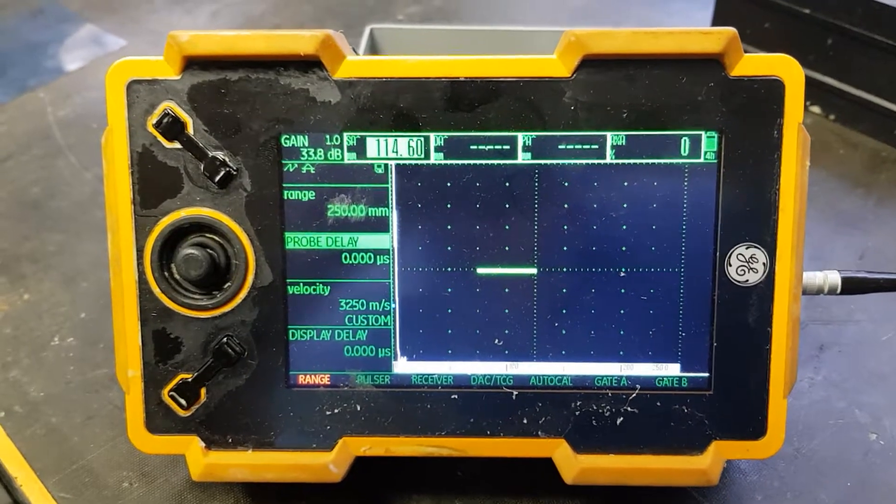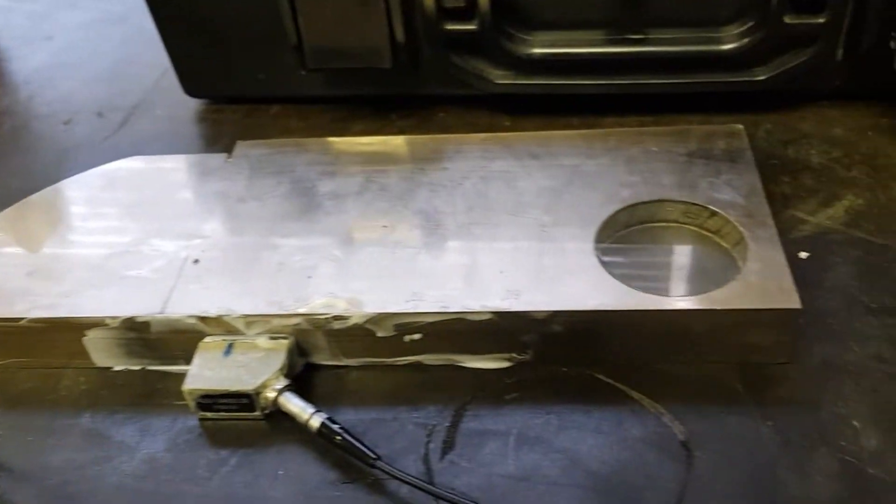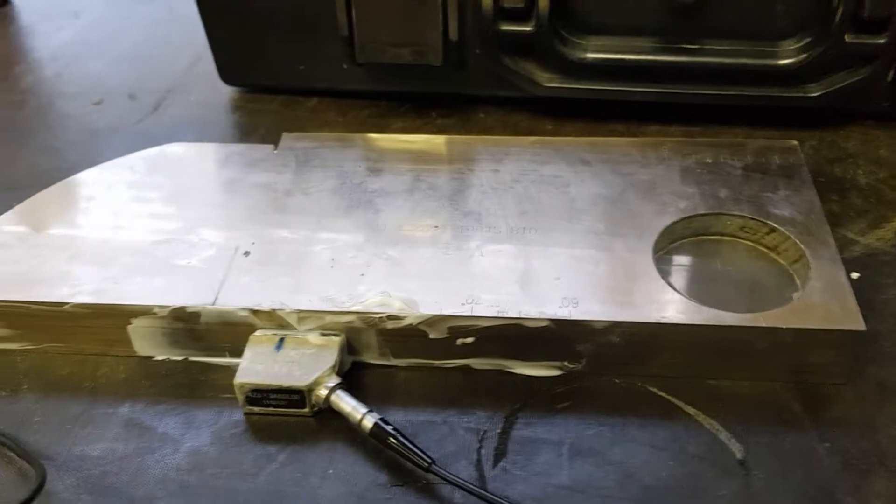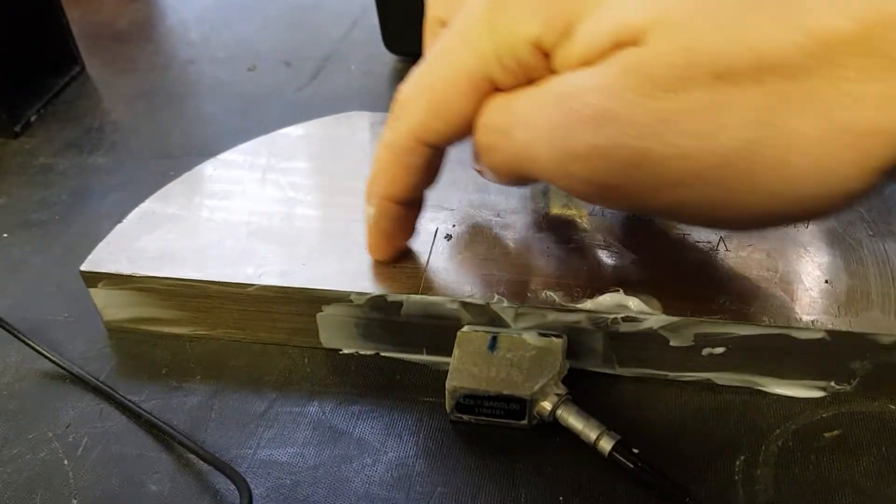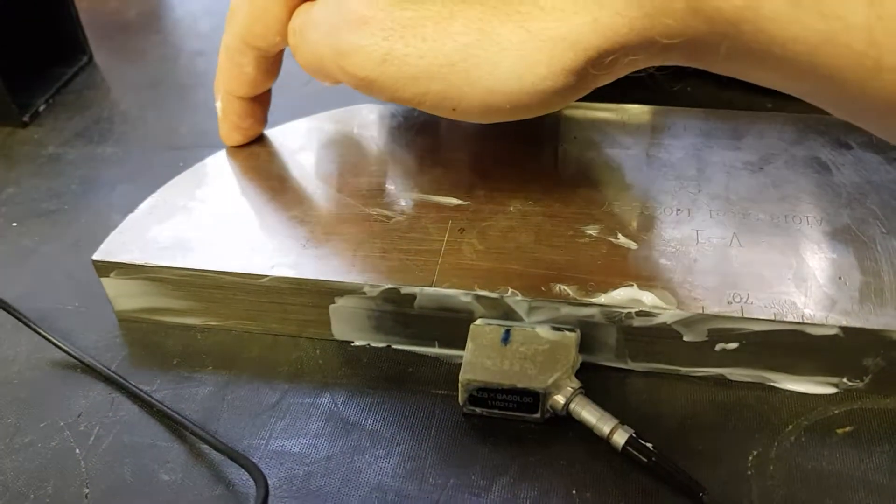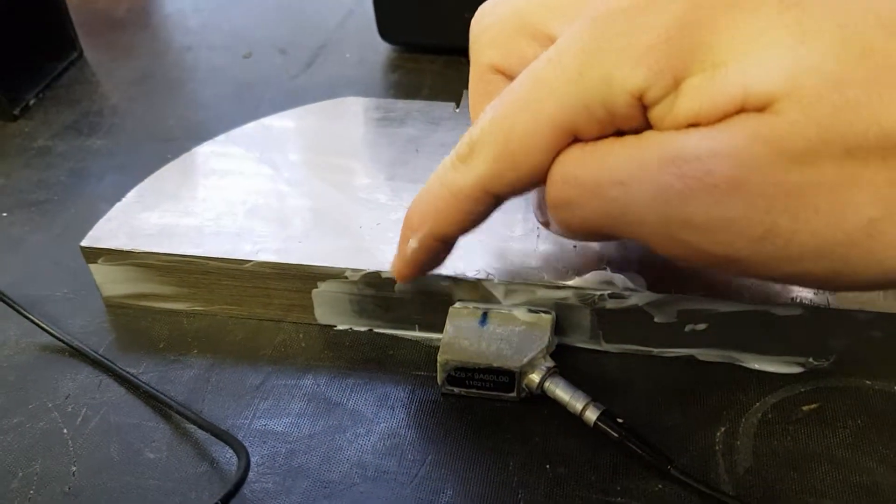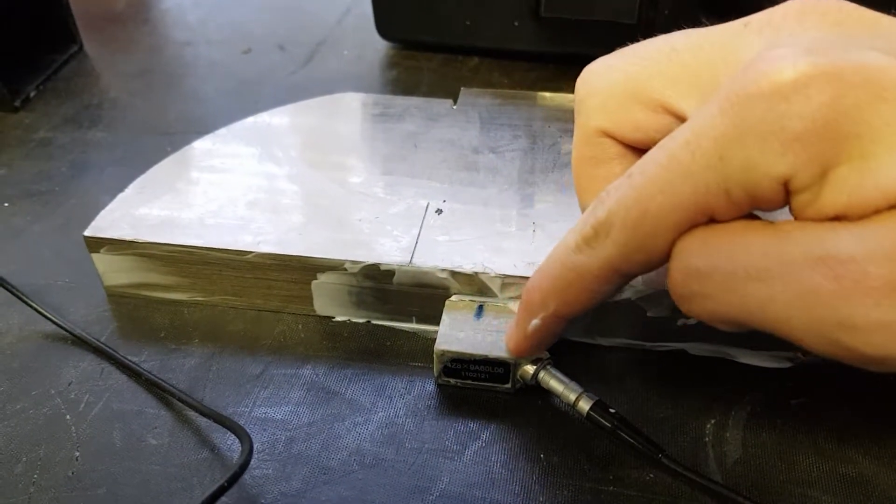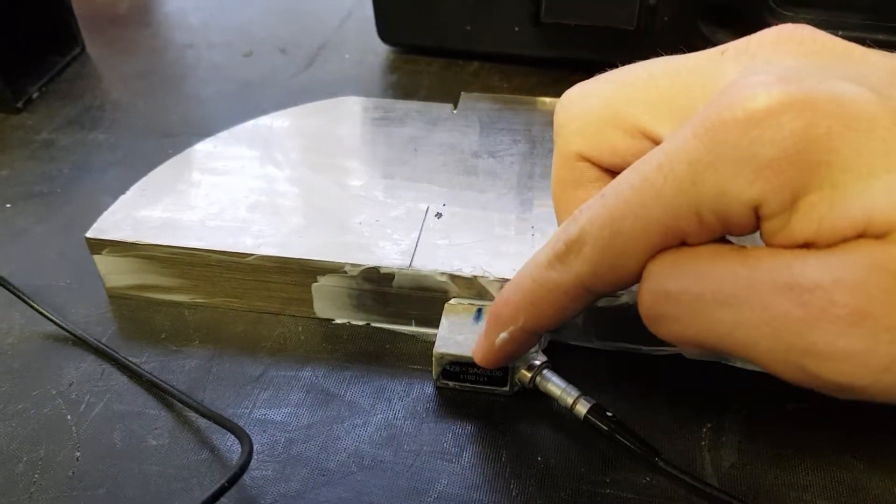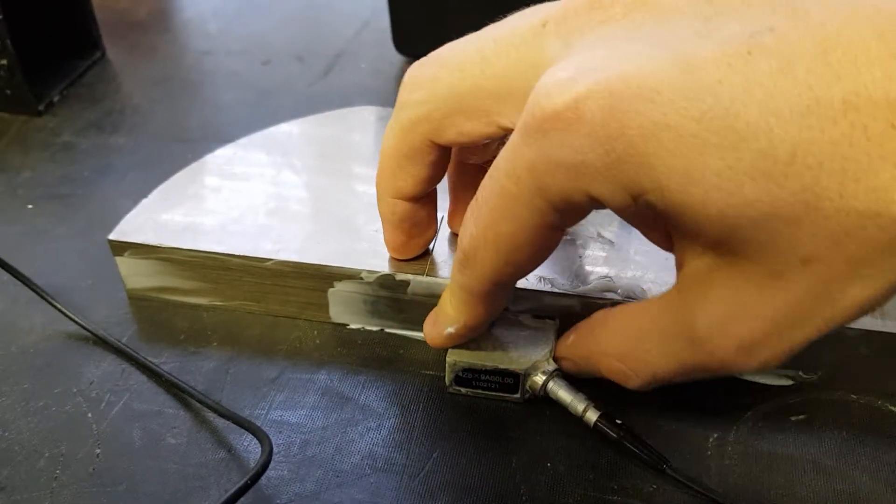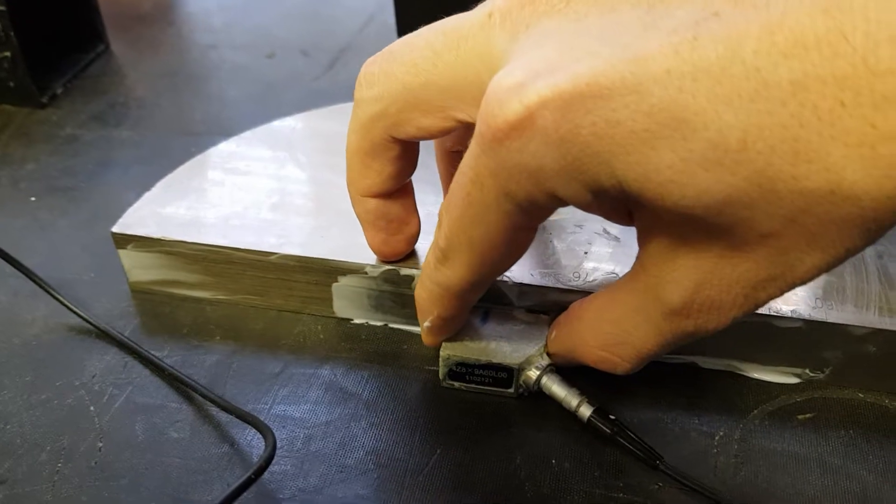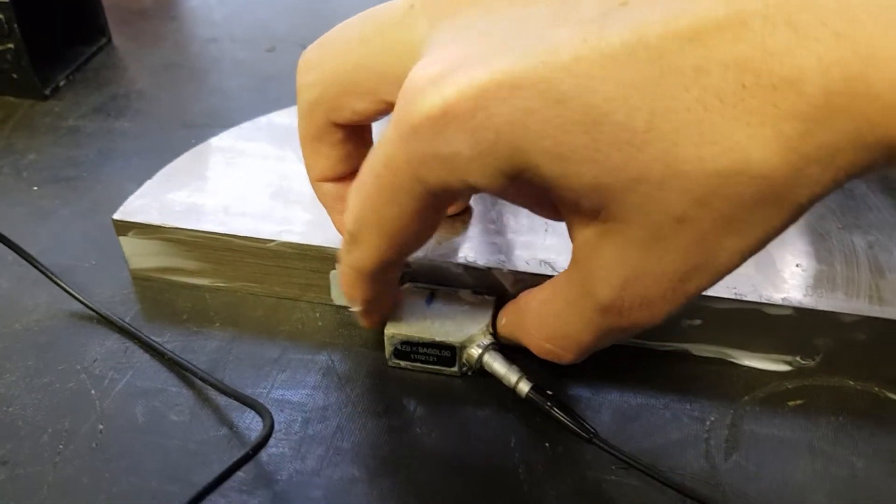The UT set has been set up with the probe coupled to the IIW block. This is a 100 millimeter radius regardless of the angle of probe being used. Whether you use a 45, 60, or 70 degree probe, the process is the same.